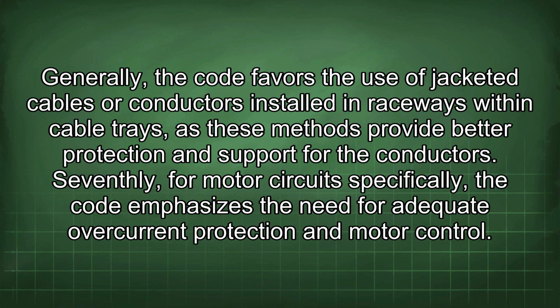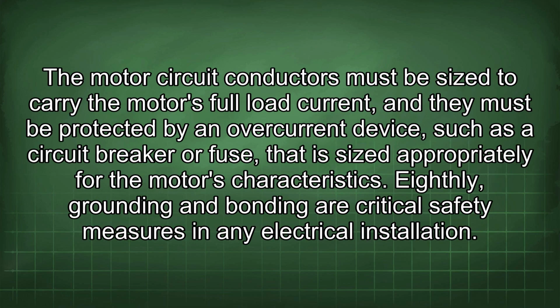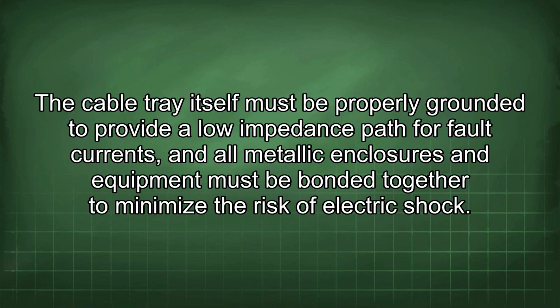Seventhly, for motor circuits specifically, the code emphasizes the need for adequate overcurrent protection and motor control. The motor circuit conductors must be sized to carry the motor's full load current, and they must be protected by an overcurrent device, such as a circuit breaker or fuse, that is sized appropriately for the motor's characteristics. Eighthly, grounding and bonding are critical safety measures in any electrical installation. The cable tray itself must be properly grounded to provide a low impedance path for fault currents, and all metallic enclosures and equipment must be bonded together to minimize the risk of electric shock.